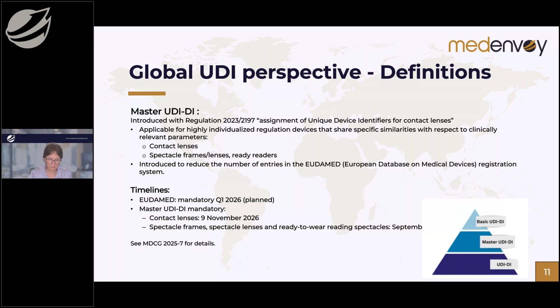Important to understand are the UDI requirements, as that is closely related to how to upload your data into EUDAMED. Each packaging level of a device will have its own UDI, starting with the lowest level of packaging, being the primary package. That UDI-DI will be referred to as your primary UDI-DI. That's the key UDI in the EUDAMED database, and it's also the UDI that is linked to the basic UDI-DI. If you have different layers of packaging, each packaging layer will have to get its own packaging DI, but only shippers, so logistic units, are exempt from that requirement.